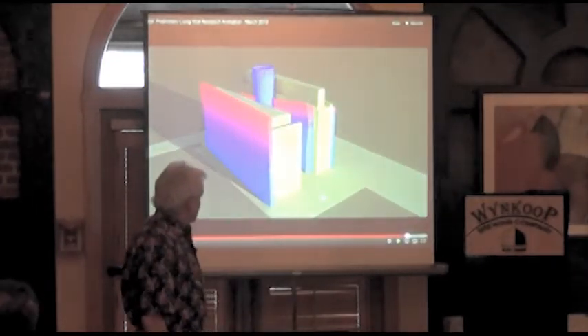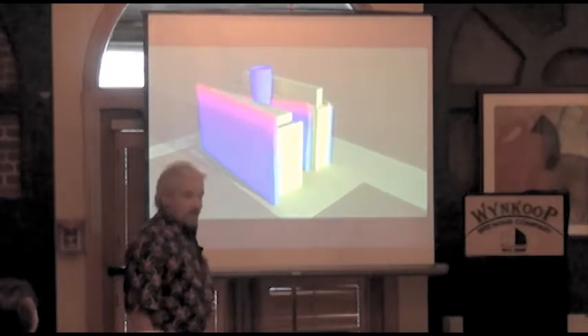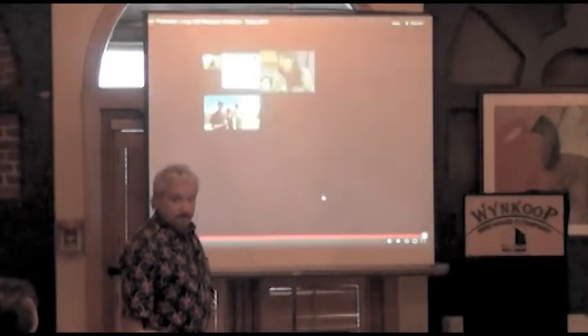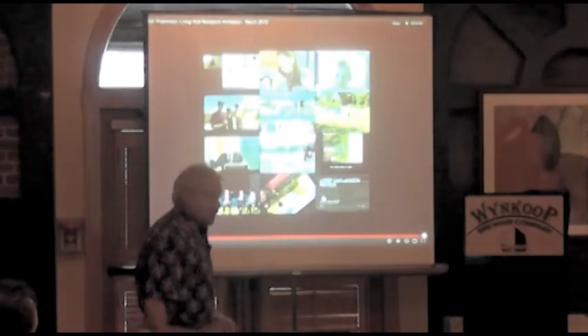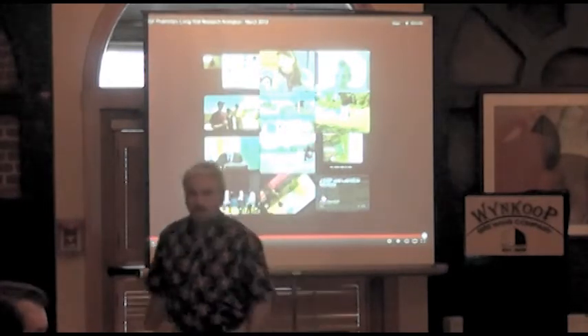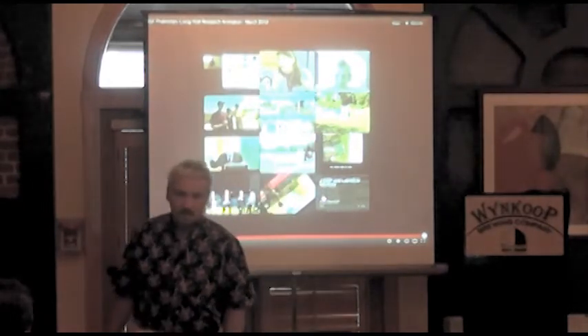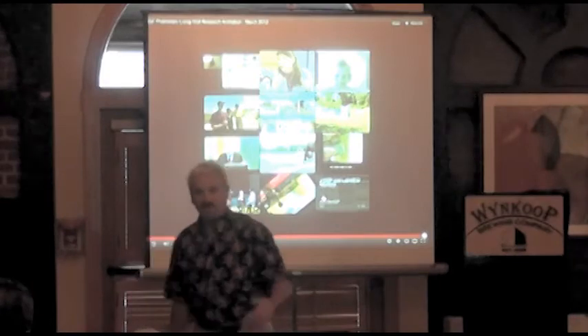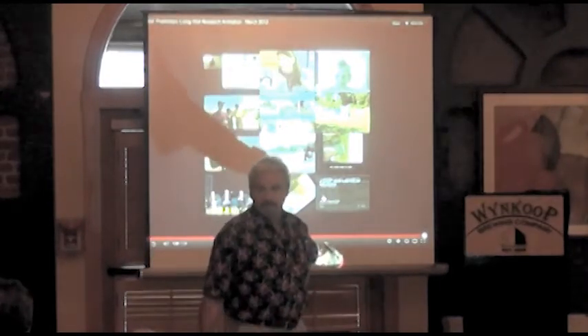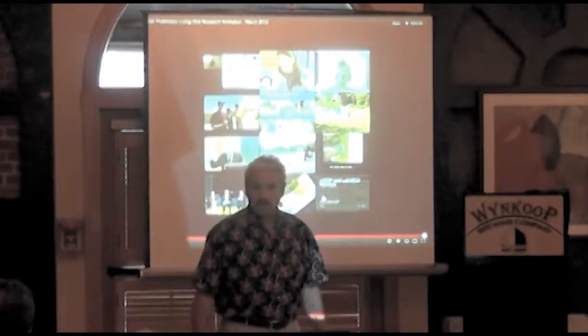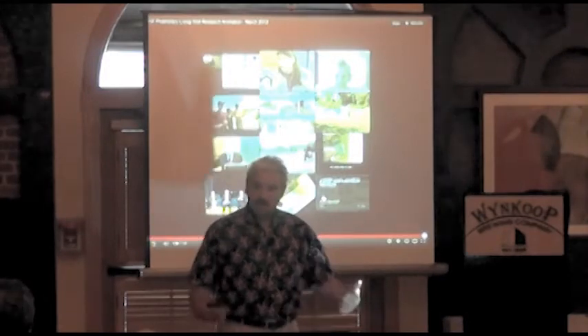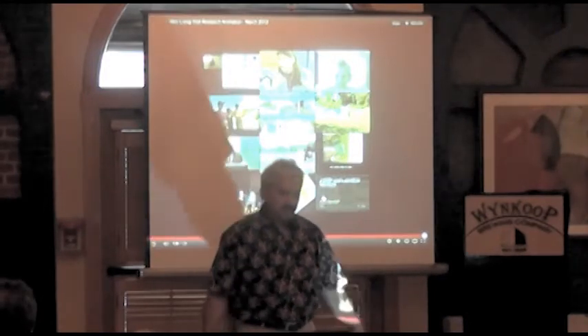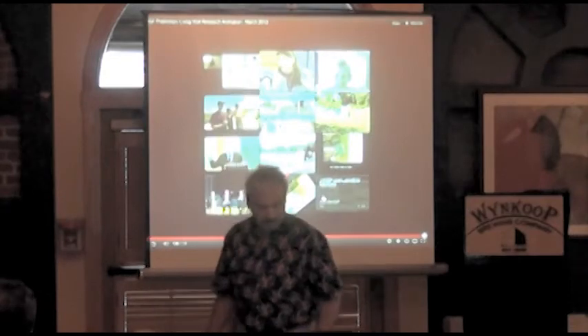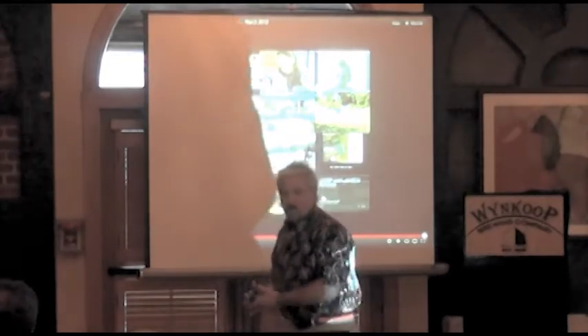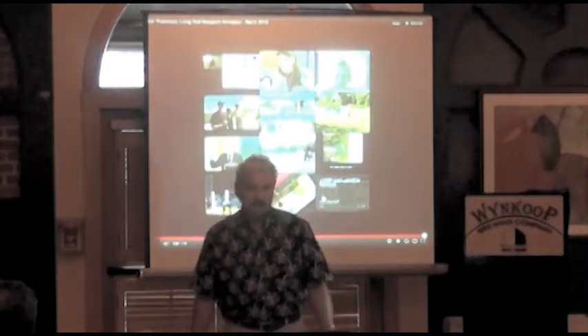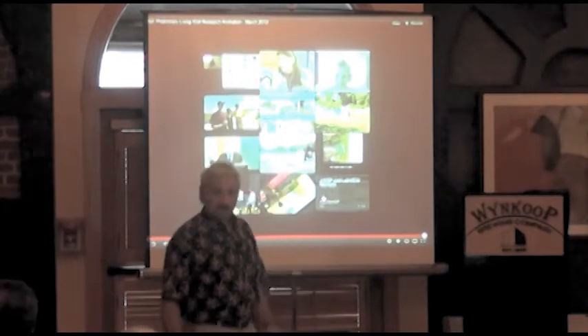Why is the cyclone so much colder than the walls? It's ground-coupled, it's 58 degrees pretty much straight up. We're able to move that volume of air you saw—270,000 cubic feet per minute. It's a lot of air. We're drawing that out, and we have a sufficient draw and cold air supply that we're able to supply it at 60 degrees. So that's why the bottom of the cyclone is so much colder.